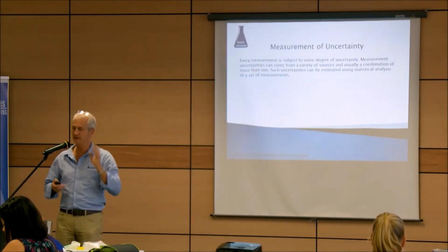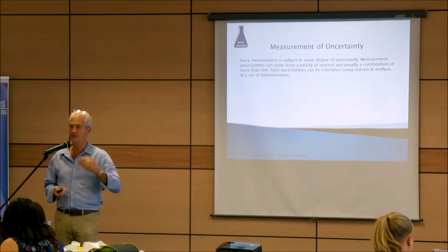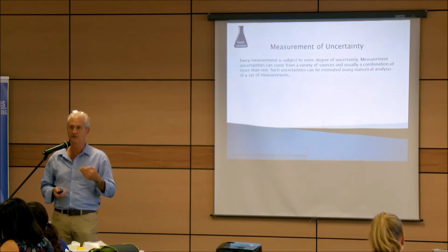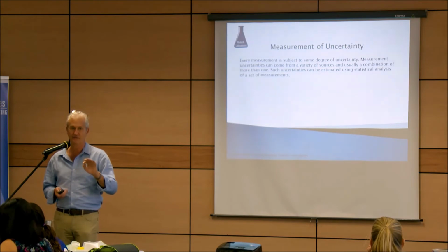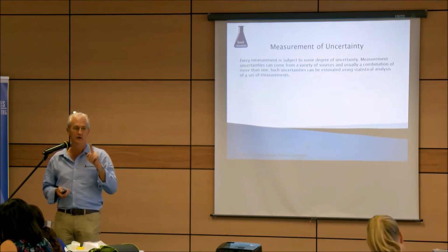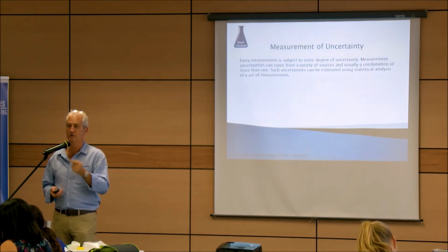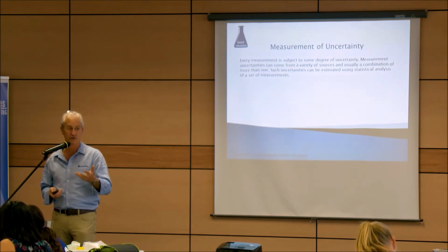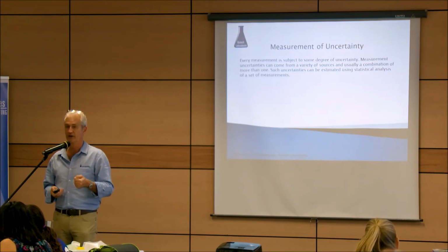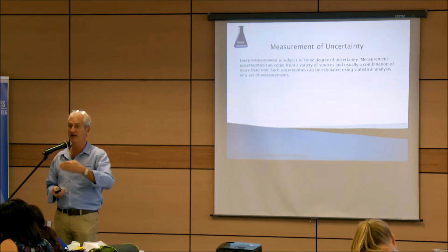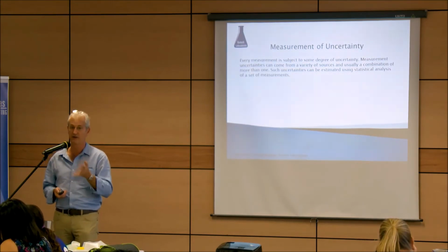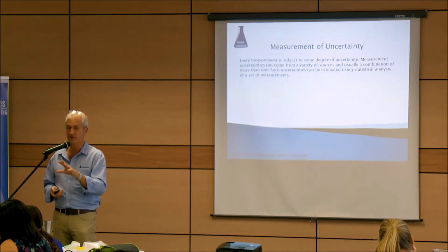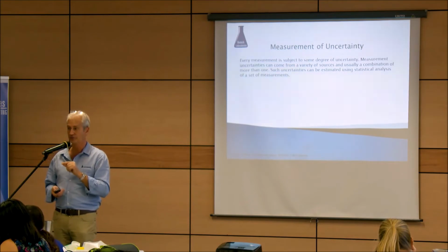Now, measurement of uncertainty, and I'll spend a little bit of time on it because it is now being made compulsory for all laboratories to report measurement of uncertainty on microbiology reports. We've been the last place to ever have had to do it, and NATA has now enforced all laboratories to do it. They must do it if they know you are using their results to compare to any guideline, whether it's your own internal or an Australian or international code. So once you tell the laboratory that, they are required to report the measurement of uncertainty. In fact, you should right now be telling your laboratory, if they are doing your testing, that you want measurement of uncertainty on all reports.